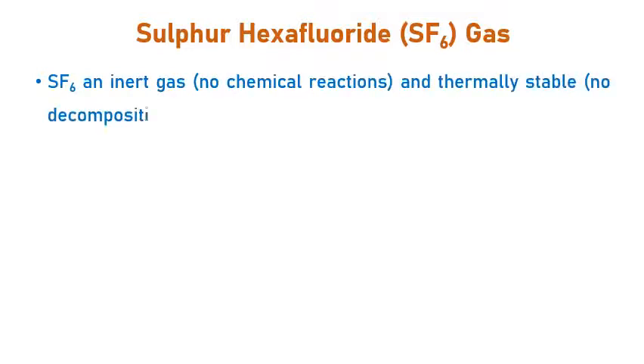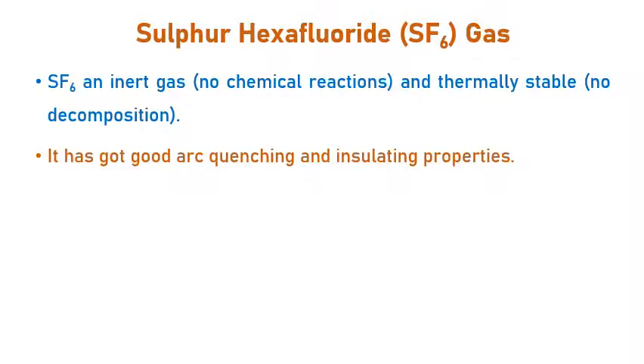SF6 is an inert and thermally stable gas. When I say inert, it means there is no chemical reaction that will occur. Unlike mineral oil discussed in the previous video on oil circuit breakers, where carbon particles are produced when oil quenches the arc, there are no such chemical reactions with SF6 gas. Thermally stable means there is no decomposition that can occur in SF6 gas. The main property of SF6 gas is that it has good arc quenching and insulating properties.